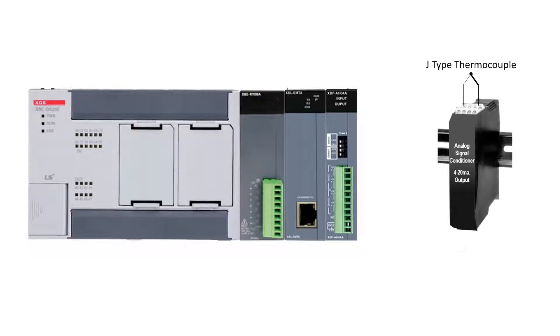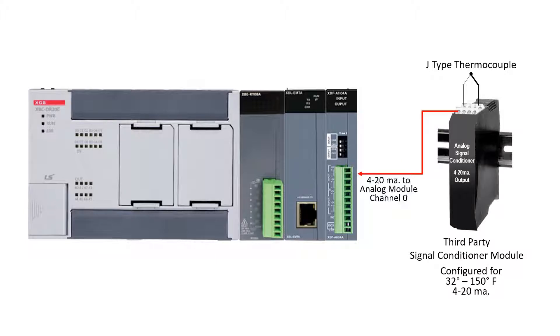The J-type thermocouple is connected to a third party signal conditioner. The signal conditioner is configured for a full scale span of 32 to 150 degrees Fahrenheit. A 4 to 20 milliamp analog signal is sent to channel 0 of the PLC analog input module. Analog channel 0 has been configured in the XG5000 programming software for 0 to 4000 counts representing 32 to 150 degrees Fahrenheit.